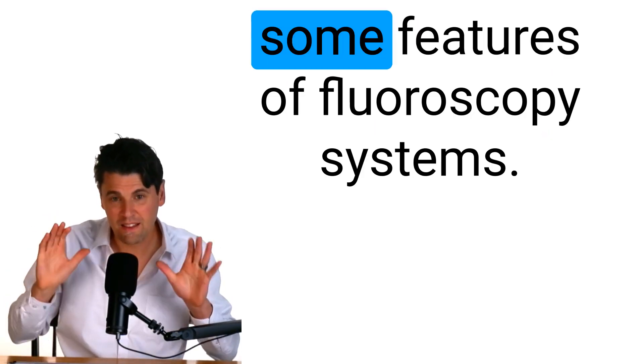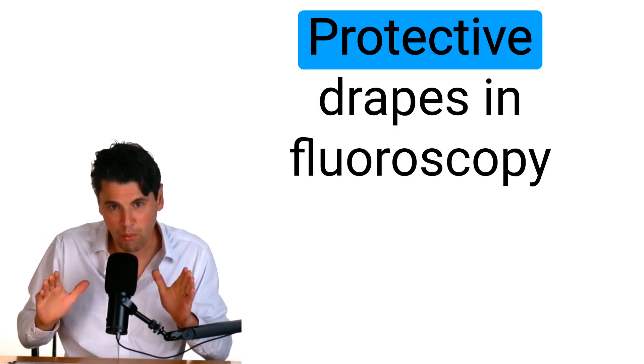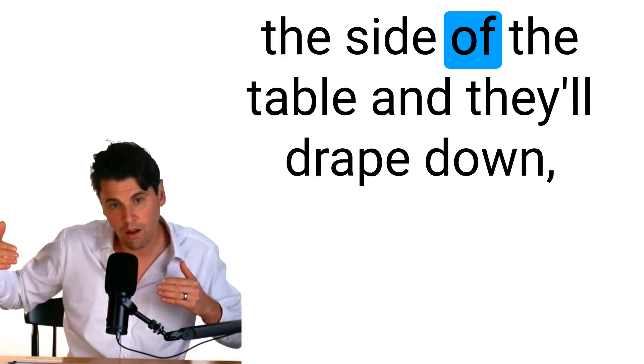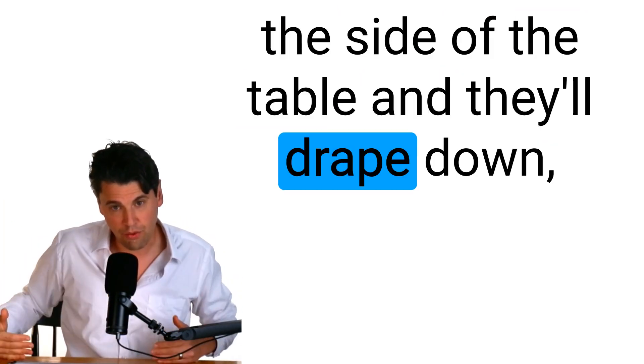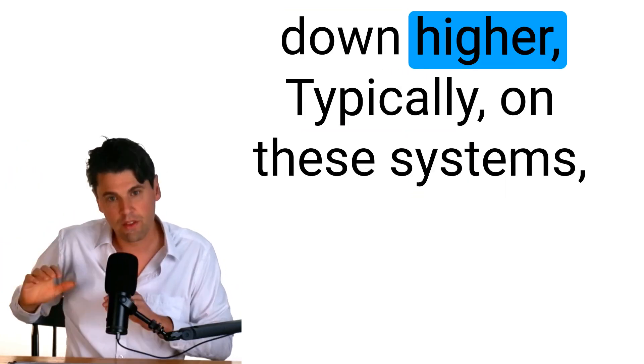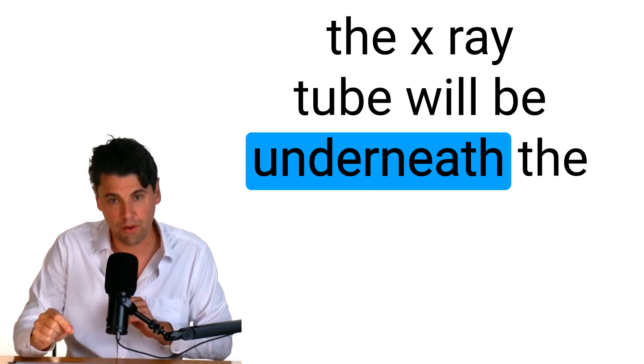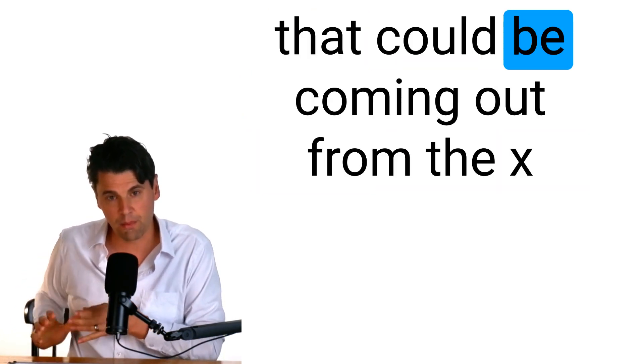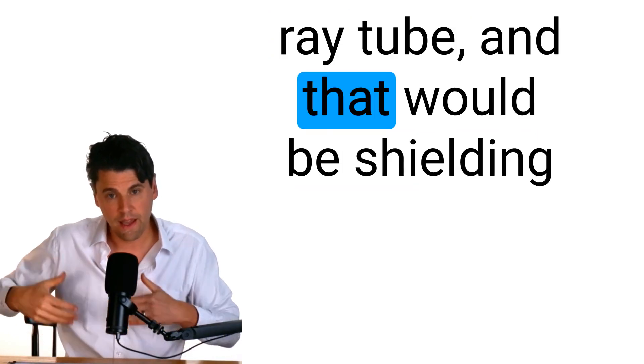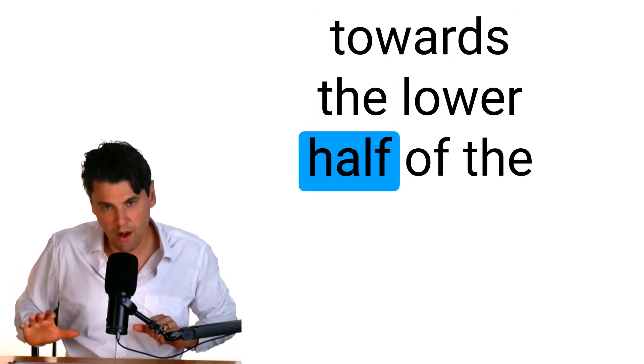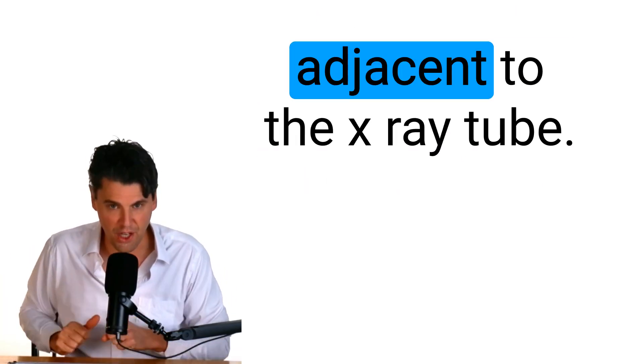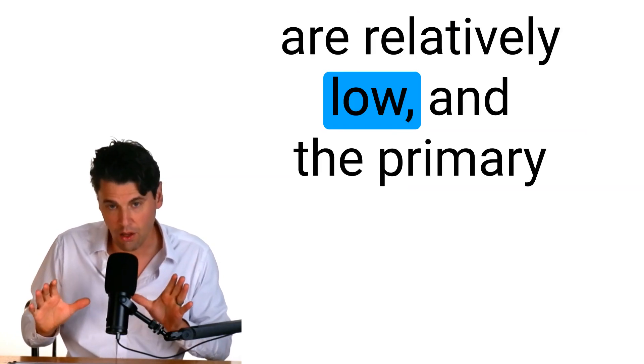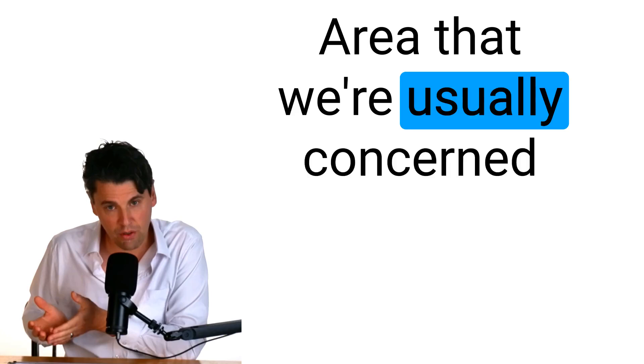Next up in this special categories is some features of fluoroscopy systems. Protective drapes in fluoroscopy systems actually are typically on the side of the table and they'll drape down. Sometimes they can even drape down higher. Typically on these systems the x-ray tube will be underneath the table. These drapes will be actually helping to shield potential stray radiation that could be coming out from the x-ray tube and that would be shielding towards the lower half of the person that's standing right adjacent to the x-ray tube.